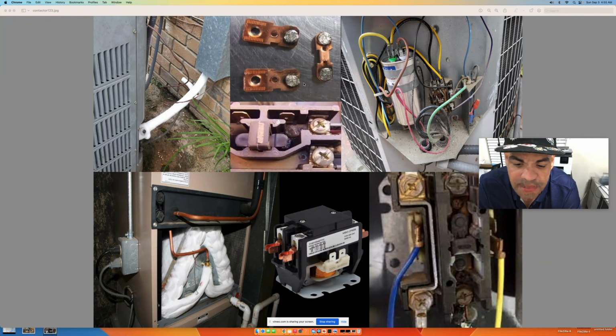So what does that mean? It means that your actual AC unit is going to be running outside. And I showed you there's some pictures here. What will happen is if your air conditioning contactor gets stuck in the closed position where it keeps on running when you have the unit off, your unit will freeze up. I showed there's two pictures here of how it looks with the frozen unit.